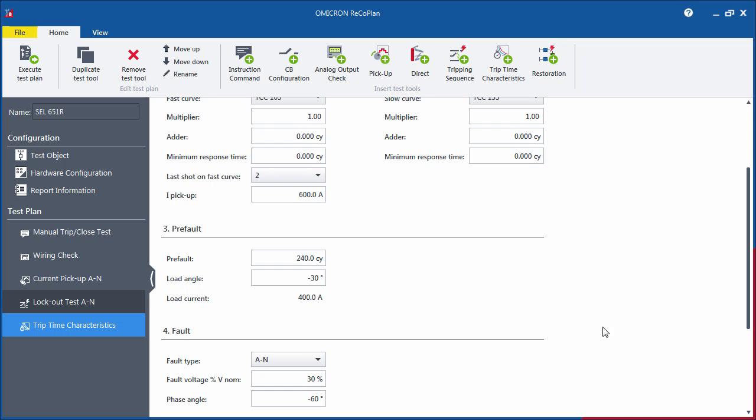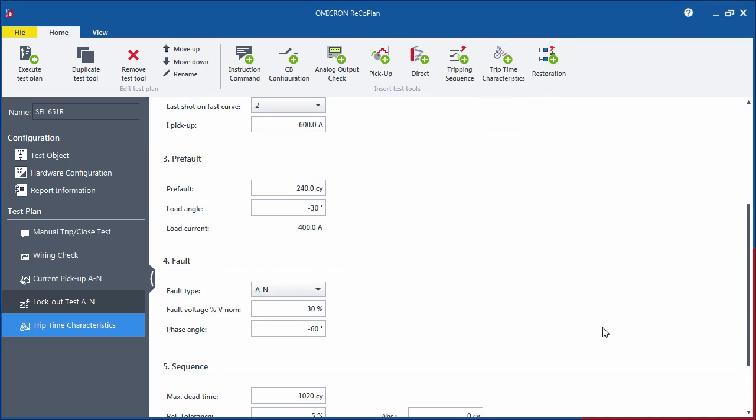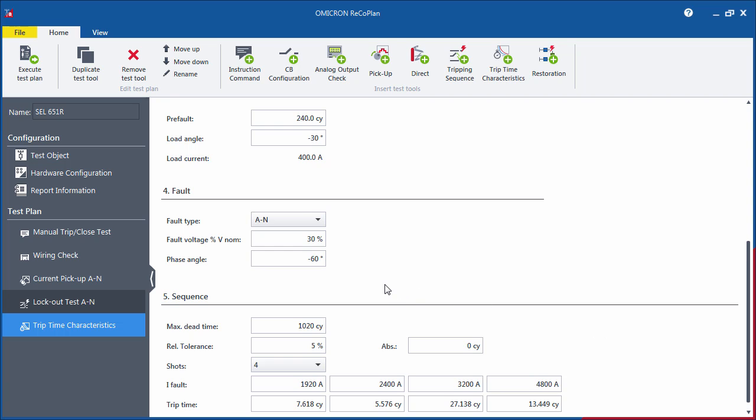The Pre-Fault section defines the pre-fault state prior to the first cycle of the test sequence. The load current will be applied during the pre-fault time.